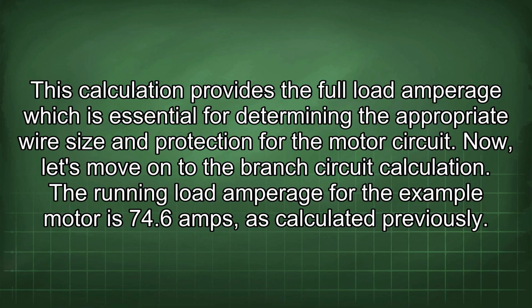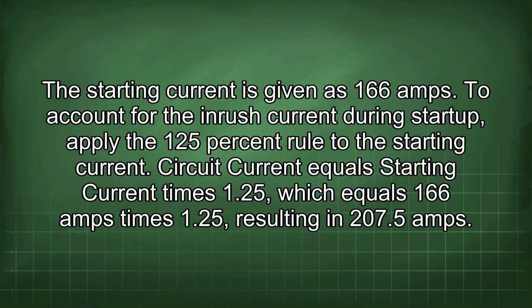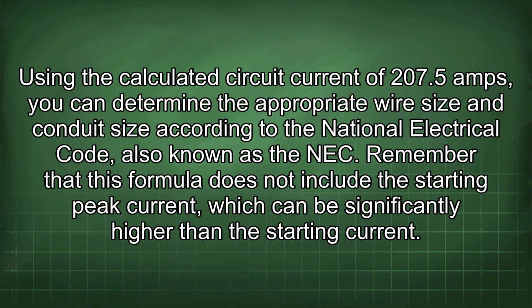The running load amperage for the example motor is 74.6 amps, as calculated previously. The starting current is given as 166 amps. To account for the inrush current during startup, apply the 125% rule to the starting current. Circuit current equals starting current times 1.25, which equals 166 amps times 1.25, resulting in 207.5 amps. Using the calculated circuit current of 207.5 amps, you can determine the appropriate wire size and conduit size according to the National Electrical Code, also known as the NEC.